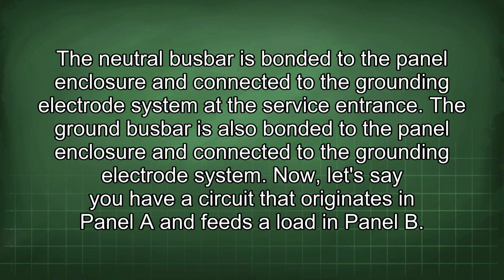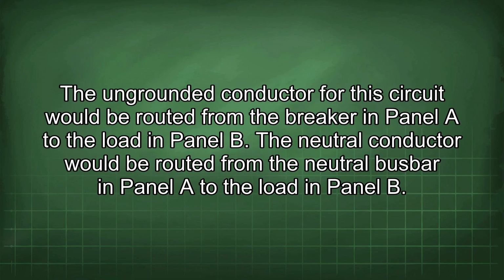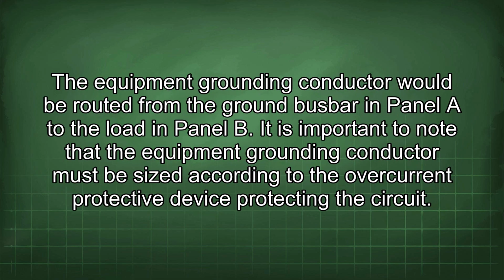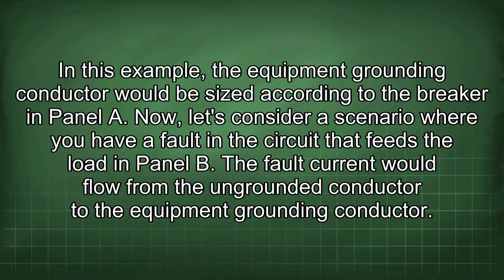Now, let's say you have a circuit that originates in Panel A and feeds a load in Panel B. The ungrounded conductor for the circuit would be routed from the breaker in Panel A to the load in Panel B. The neutral conductor would be routed from the neutral busbar in Panel A to the load in Panel B. The equipment grounding conductor would be routed from the ground busbar in Panel A to the load in Panel B. It is important to note that the equipment grounding conductor must be sized according to the overcurrent protective device protecting the circuit. In this example, the equipment grounding conductor would be sized according to the breaker in Panel A.